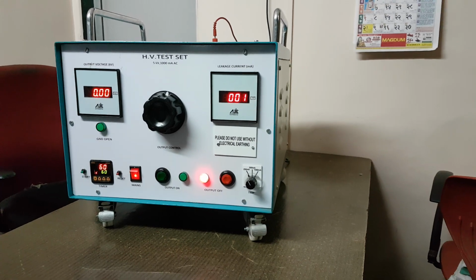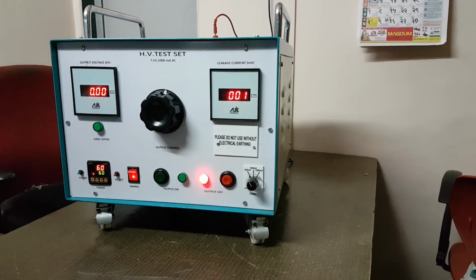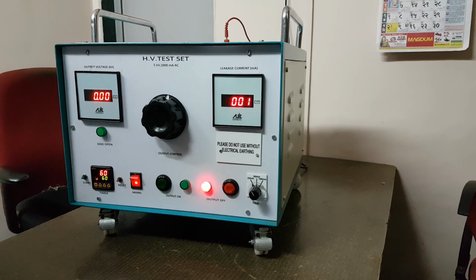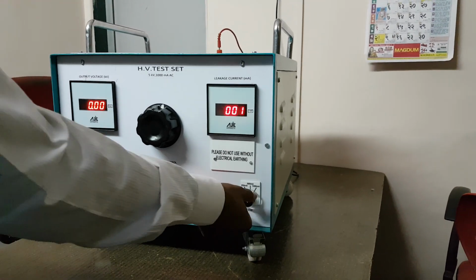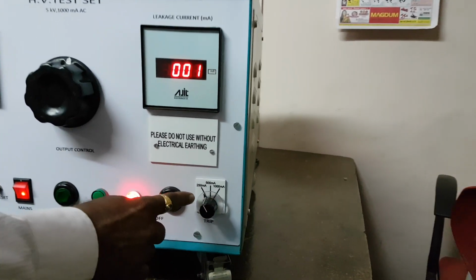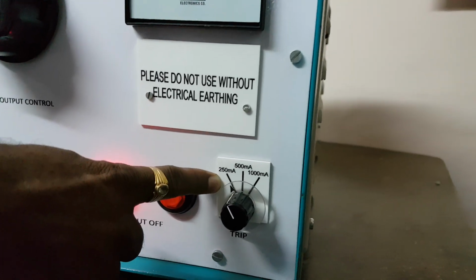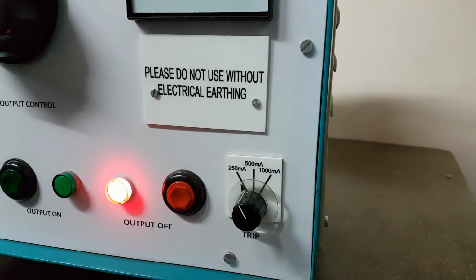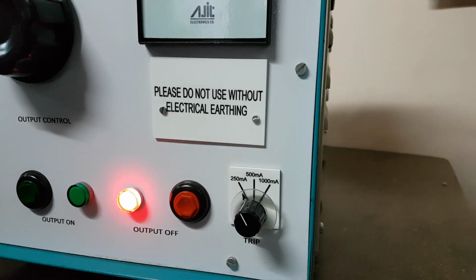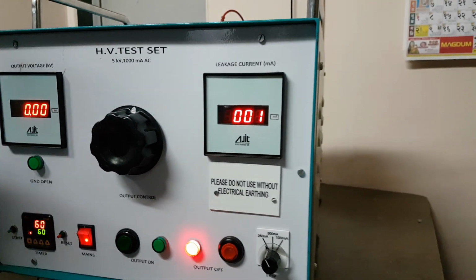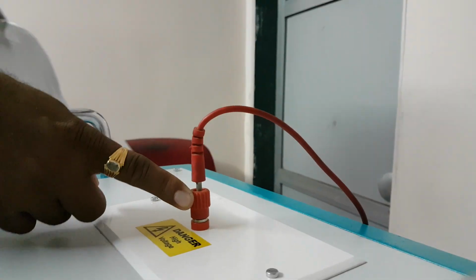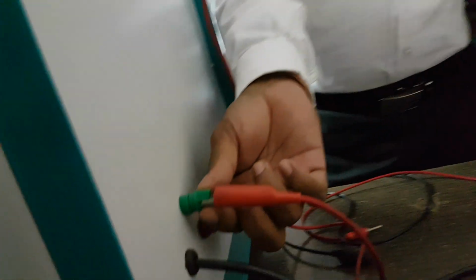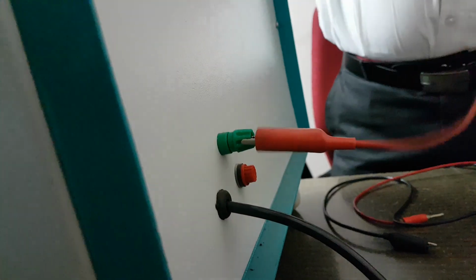Now let's see the overcurrent trip facility in the instrument. For that, we have to select the trip current range. I have selected 250 milliampere here, and we have to short the output to the ground. Here the output terminal is provided. This one is the output terminal, and we have to connect this to the ground terminal. This green terminal is the ground terminal. Here I have put a shorting link.